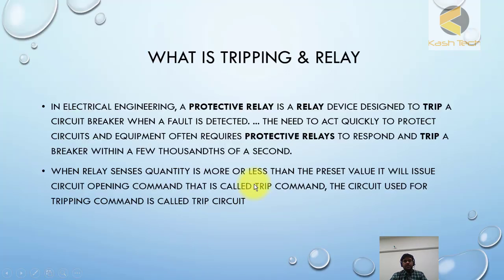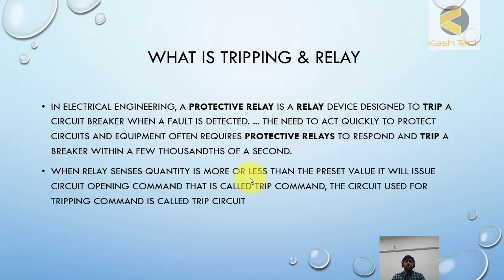What is tripping and what is a tripping relay? In electrical engineering, a protective relay is a relay device designed to trip a circuit breaker when a fault is detected. The need to act quickly to protect circuits and equipment often requires protective relays to respond and trip a breaker within a few thousands of seconds or milliseconds. When the relay's sensed quantity is more or less than the preset value, it will issue a circuit opening command — that is called a trip command. The circuit used for the tripping command is called the trip circuit.